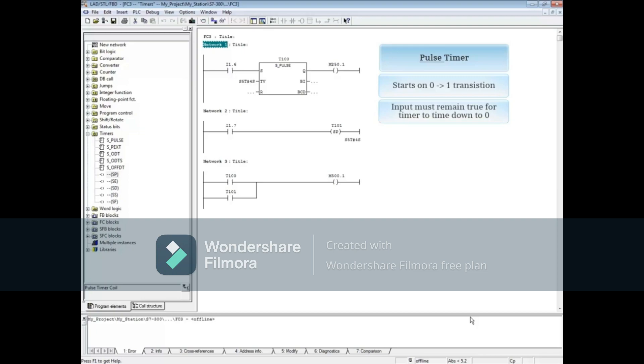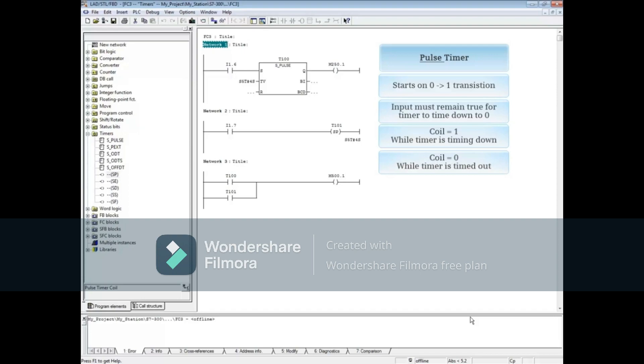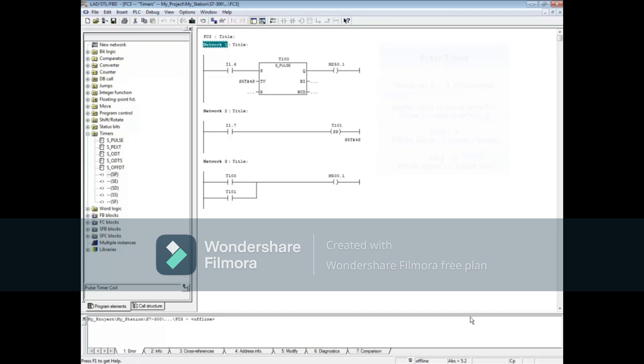The input must remain true for the timer to time to 0. The coil is 1 or true while the timer is timing down, and the coil is 0 when the timer has timed out. Each time the input transitions from 0 to 1, the timer automatically restarts.